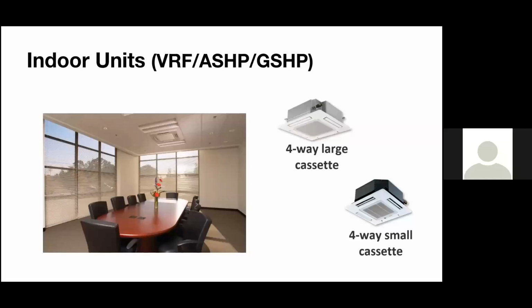Nice thing about the larger cassettes, they do have more capacity. And also you have your return in the middle with a filter, right? But what's nice is on the larger ones, you can open that up and actually service it from the bottom. You do not need an access door. And then you have your supply air coming out on all 4 vanes, and these can be adjusted through controls. And then the small cassette, same kind of setup, except you do need to have an access panel, which shouldn't be a problem for a drop ceiling like this, but you do need an access panel for these smaller cassettes.